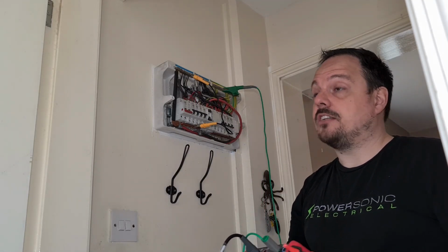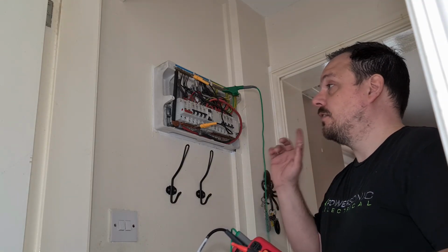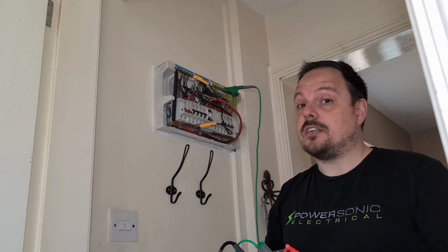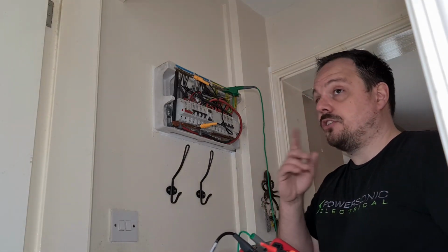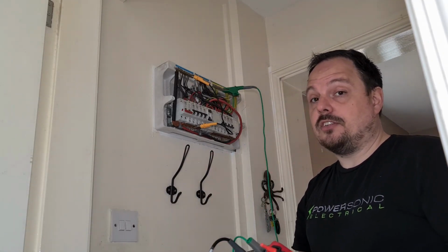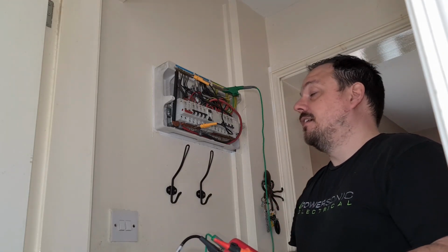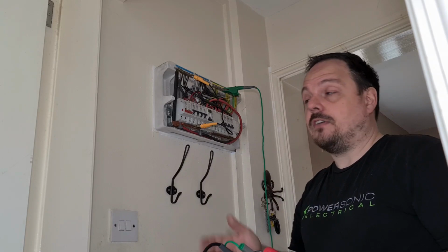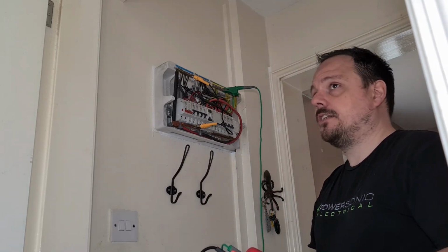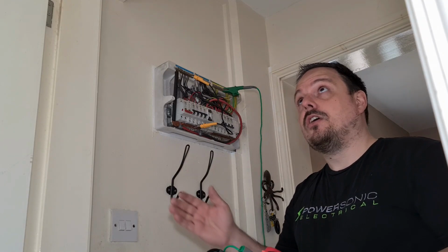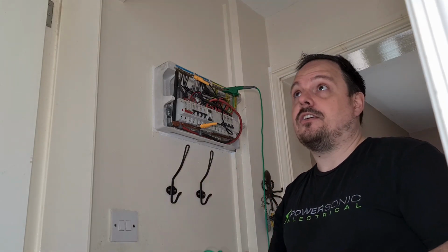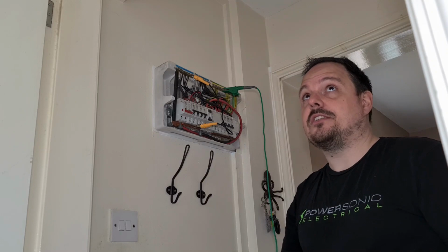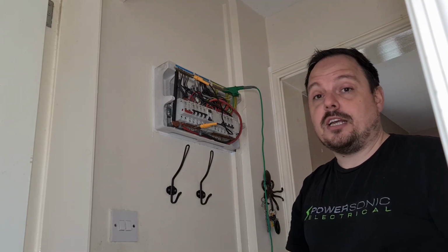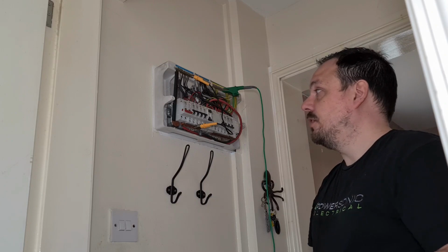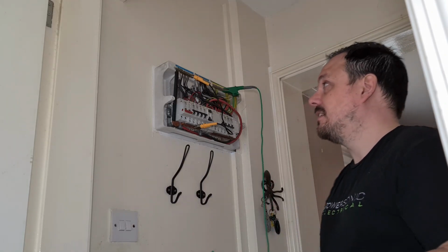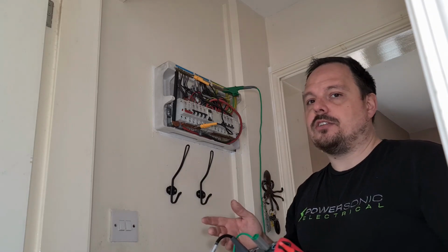I'll go and take some of the accessories off. I can do that quite easily on the upstairs lighting circuit, and we'll see if the cabling itself is clear. It could be that some of the moisture's tracked back down that cabling and we've had a breakdown of the insulation. If that turns out to be the case, even though it's reading at an acceptable value, I'd be very unwilling to return that to long-term service, having had all the plasterboard stripped off and new kitchens fitted and other bits and pieces, just for the sake of pulling in some new cable to get those values back up to good as new. I think it's a bit foolish. So that's the way I'm going to be approaching this one.